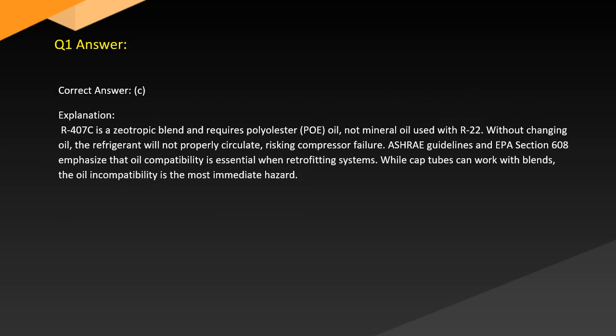Answer. Correct answer, C. Explanation. R407C is a zeotropic blend and requires polyolester POE oil, not the mineral oil used with R22. Without changing oil, the refrigerant will not properly circulate, risking compressor failure. ASHRAE guidelines and EPA Section 608 emphasize that oil compatibility is essential when retrofitting systems. While cap tubes can work with blends, the oil incompatibility is the most immediate hazard.